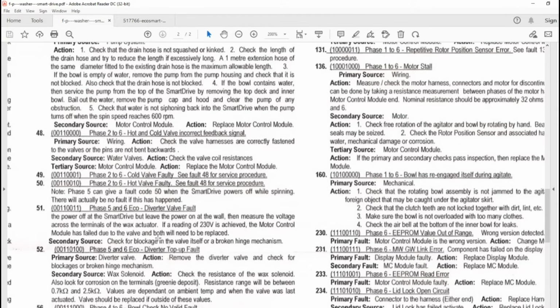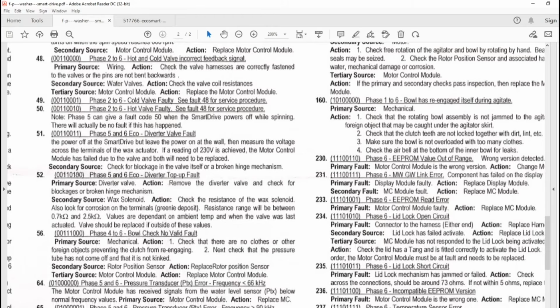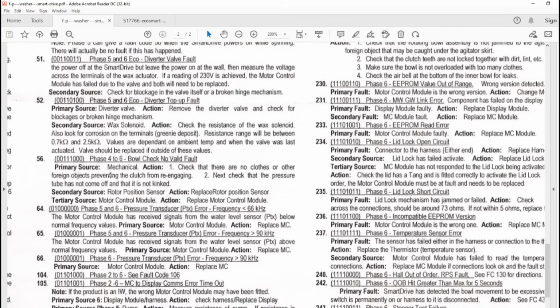Now one of these, here we go, diverter top-up fault. So if you've got an eco machine, and we'll talk about eco faults, eco getting the diagnostics later, but if you've got an eco machine and the diverter valve has got a blockage in it, when it goes to recirculate for eco, you actually end up pumping some water out, so this 52 pops up, and that's usually a blockage in the valve itself. Or it can be a faulty valve which is not sealing, but you've got to check for blockages.